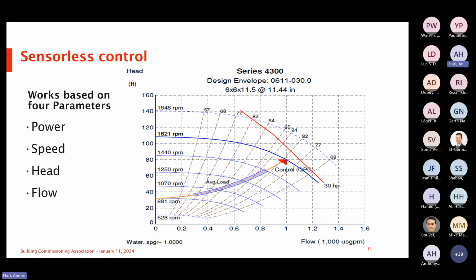I'm going to stop here because a lot of times people ask, how does this work? First of all, in our industry, every single centrifugal pump uses what we refer to as a variable torque motor. What that means is that the motor will only do the work required based on the resistance on the shaft, and it will only draw the power required to overcome that resistance. So if I have a 200 horsepower pump, and just for the sake of making this simple, we'll use a linear relationship, we'll say that a 200 horsepower full load amps is 200 amps.